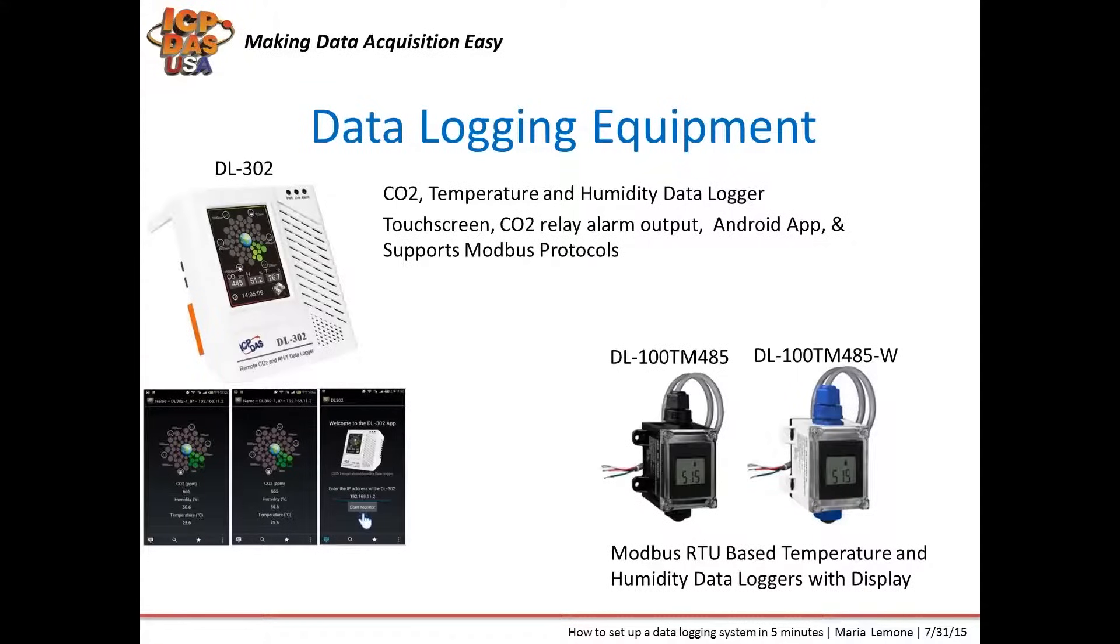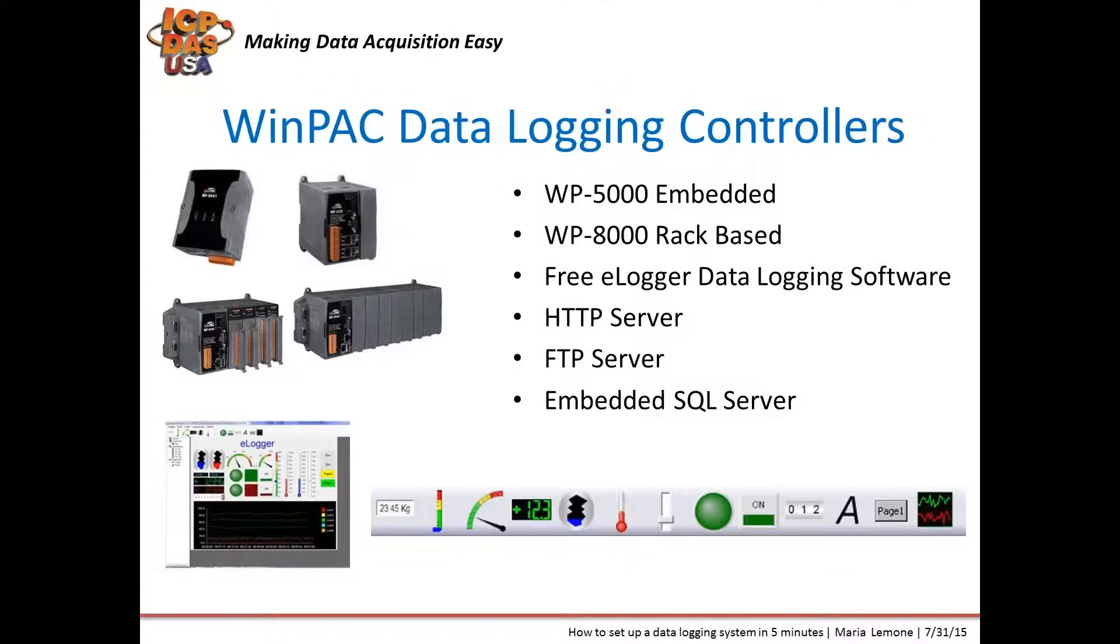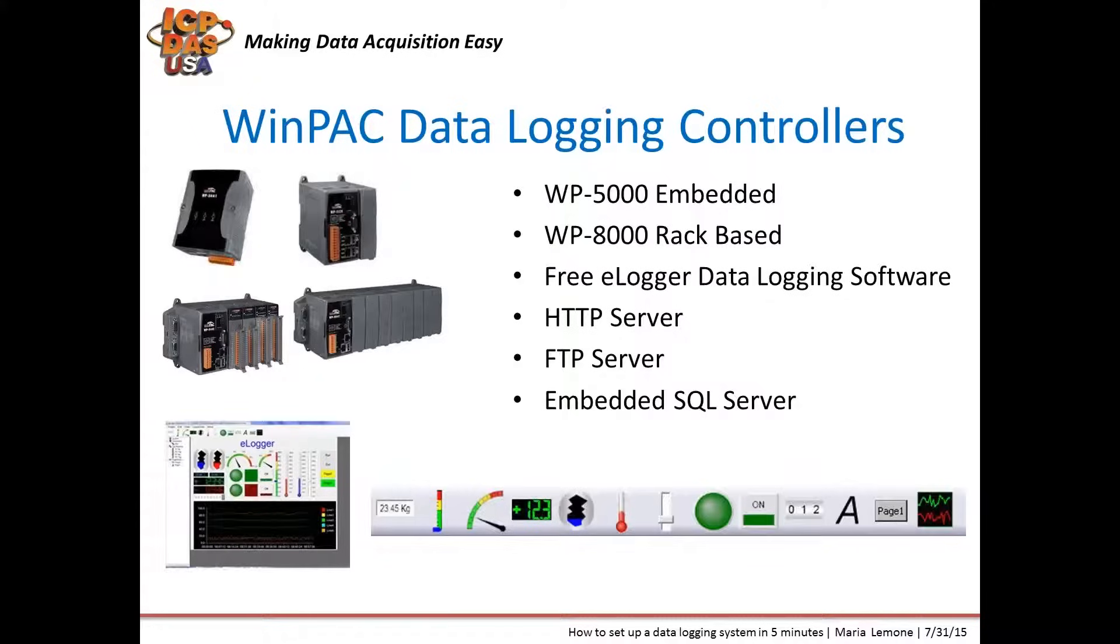The WinPAC programmable automation controllers with WinCE.NET operating systems come with free configurable eLogger data logging software. With eLogger you can log data and can design screens for displaying information. The screens can have buttons that can be used to start or stop projects and also turn I.O. on or off. WinPACs have Ethernet, USB, RS-485, RS-232, and VGA ports. The WP5000 embedded type can be used with expansion I.O. boards that can go inside. The WP8000 rack-based types can be used with I.O. cartridges that slide in the rack. They all can be used with remote I.O. modules and Modbus equipment. You can publish eLogger software to their HTTP servers for displaying information through a web page. You can transfer data log or other files with the FTP server. You can log data to the embedded SQL server database.